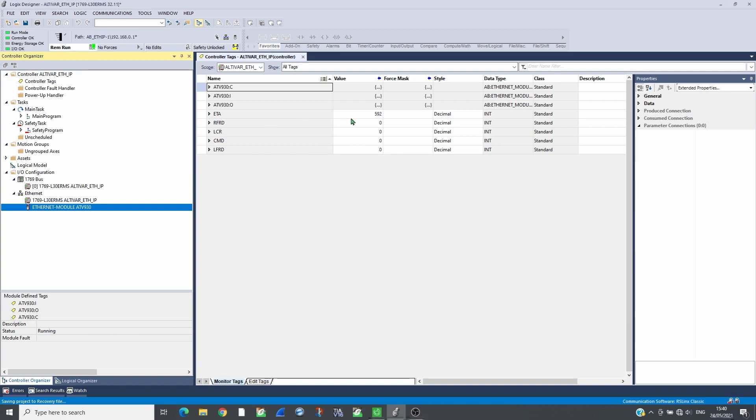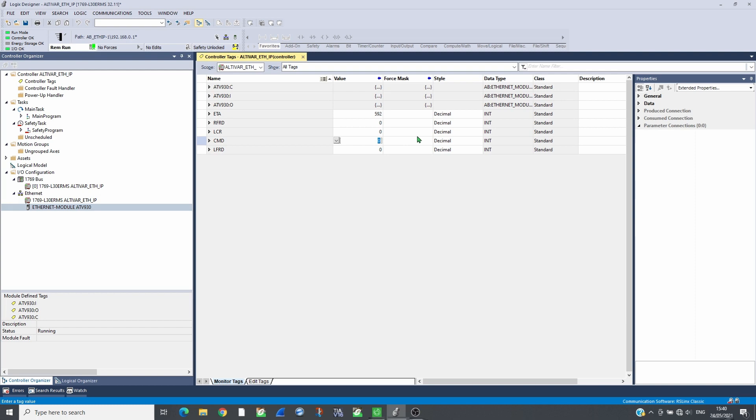By following the CIA402 profile, the drive can be controlled. Send 6, then 7 in command and the drive will switch into ready state, ETA563.